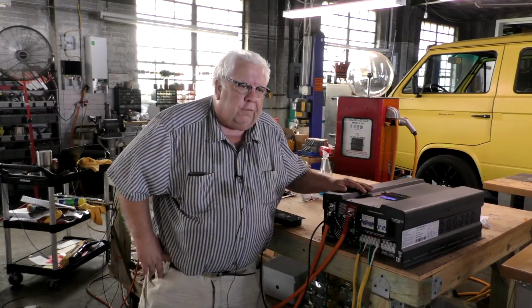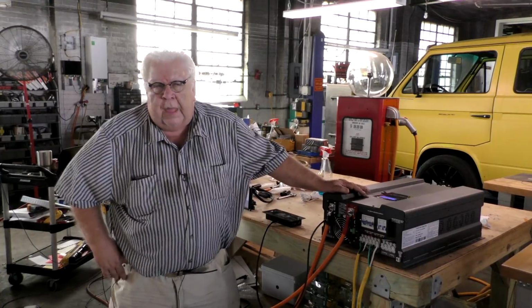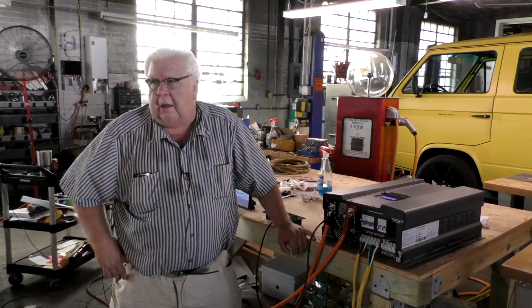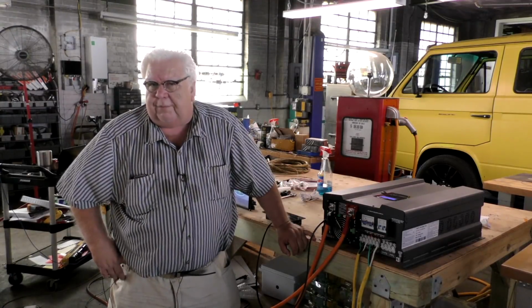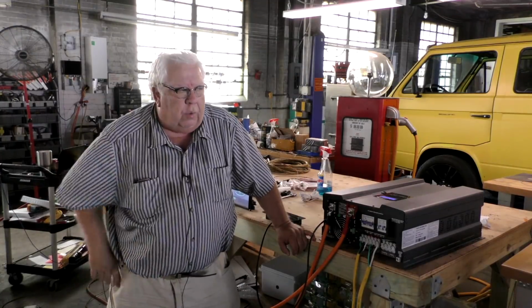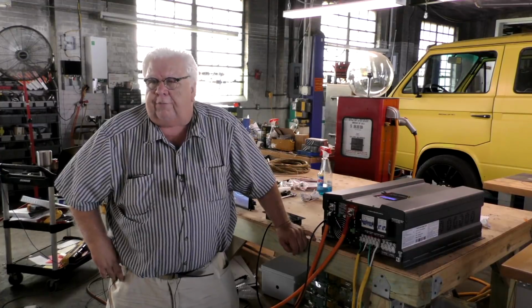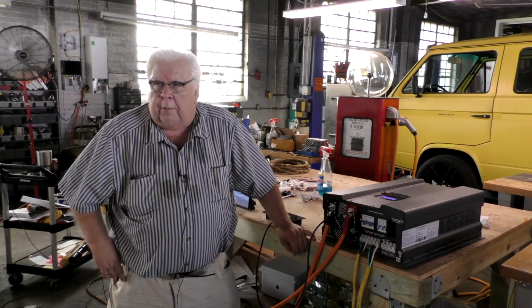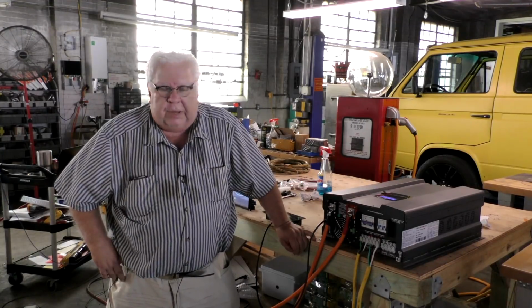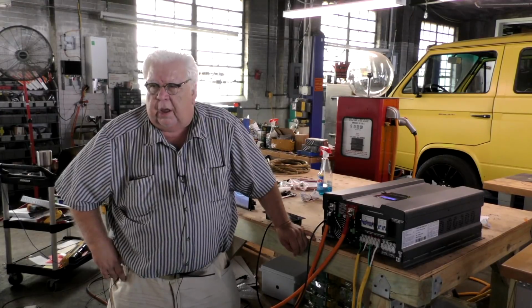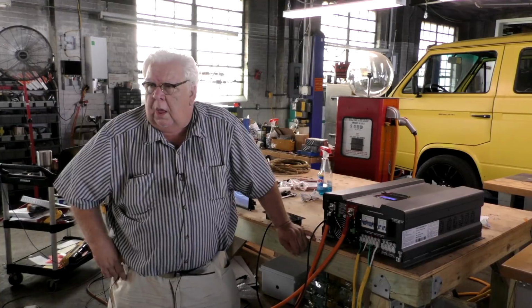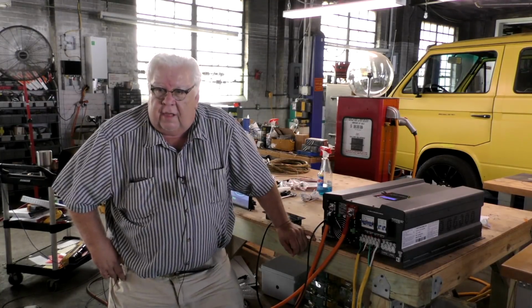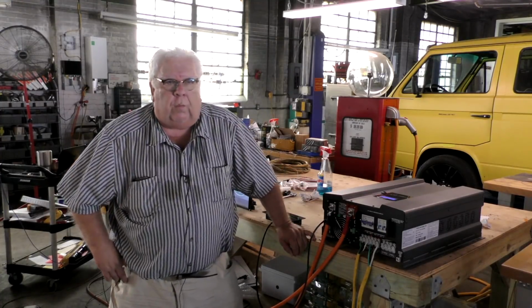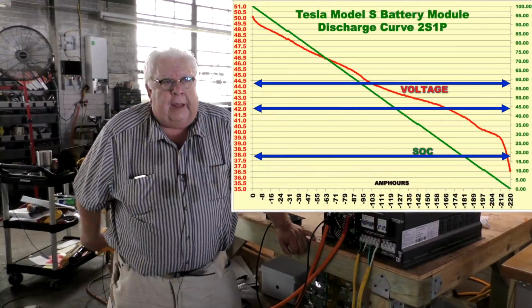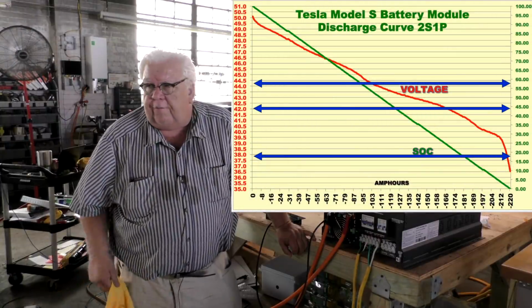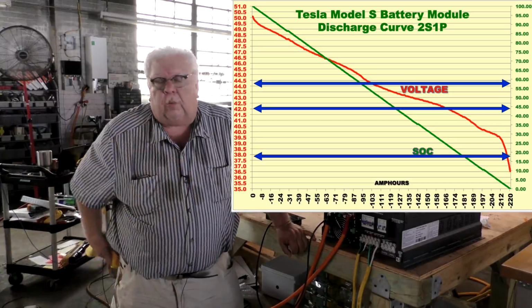And that takes us to the inverters and the charge controllers and so forth for 48 volts. They are seriously misapplied. And it's very simple stuff, but it's very difficult to get these people to change in the early days. Later, they will change it just fine. But right now, they're all set up for lead-acid batteries or for lithium batteries with a variety of BMS CAN communications parameters, very complicated systems, needlessly so. But the bottom line is they're accustomed to charging to 56 volts, equalizing at 60, and have a low voltage cutoff of 42 to 44 volts. That just doesn't work with Tesla batteries.